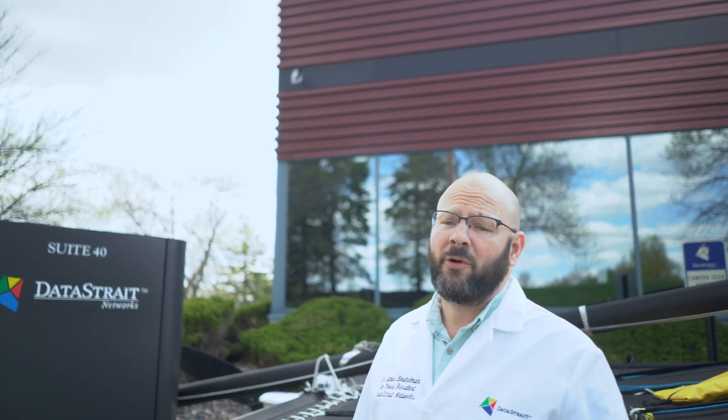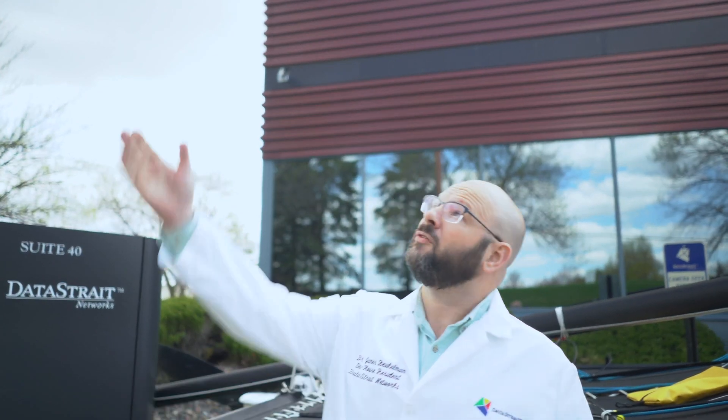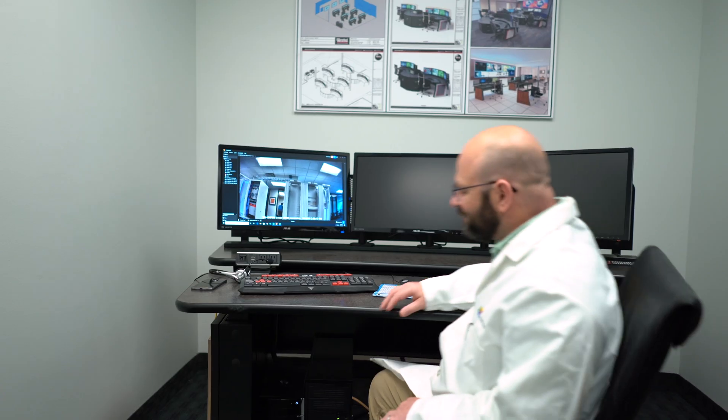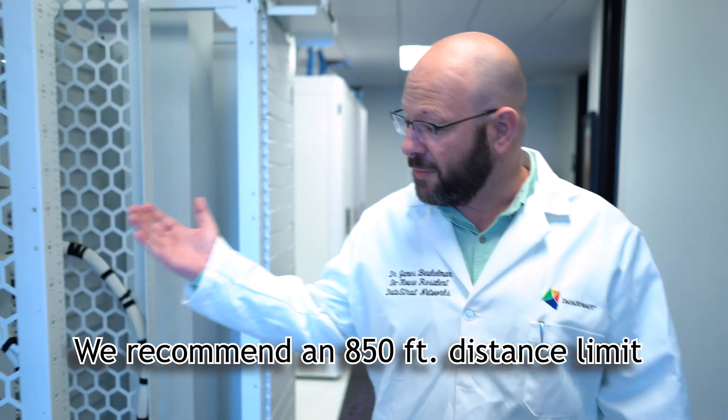This type of product would be perfect for running cameras on the corner of buildings, whether it be a warehouse or a school, where it's over that 100-meter limit to get to the camera. It would also be perfect to put on a pole out in a parking lot. We here at DataStrait don't recommend you ever go beyond the manufacturer's stated limits, but we have proven today that across 1,000 feet of cable, we can run PoE and cameras. Should you have any other questions, please reach out to your DataStrait representative.